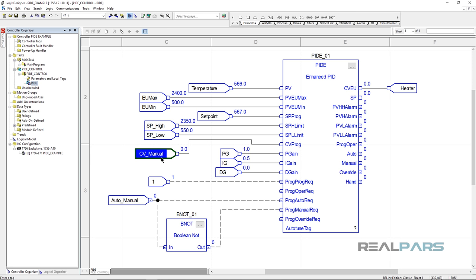The PIDE will need to be tuned. We have to set the tuning parameters: PGAIN to 1, IGAIN to 0.5, and DGAIN to 0 as a recommended starting point. PID tuning can be tricky, so I recommend reviewing procedures for this technique. The standard reference for PID tuning seems to be the Ziegler-Nichols tuning rules.